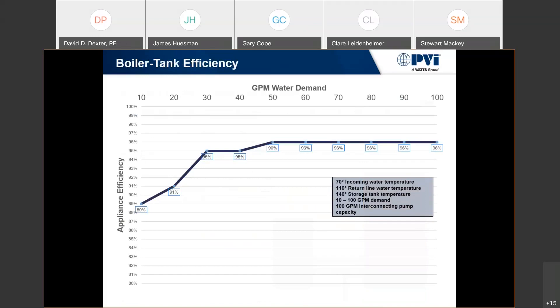Because of that scenario, any boiler-tank or instantaneous with a storage tank will have an efficiency curve where under low demands — the x-axis is GPM, the y-axis is appliance efficiency — you're actually below 90%. As flow or demand in the building increases, we're introducing more cold water into that heat exchanger, and that drives the efficiency of that appliance. That's why efficiency curves on instantaneous units look the way they do.